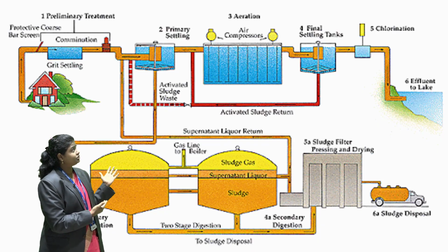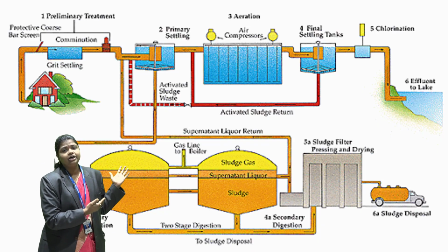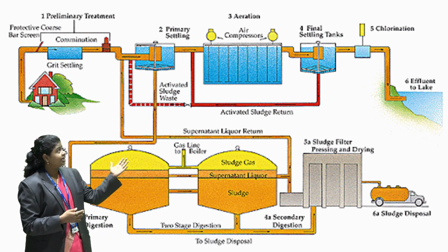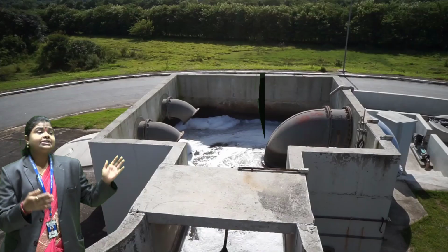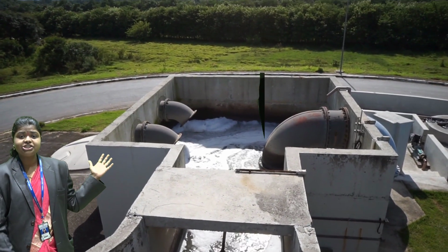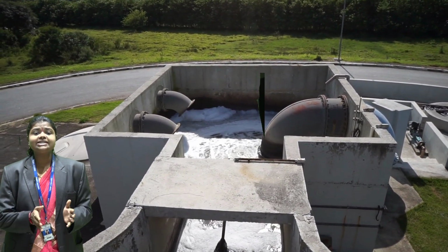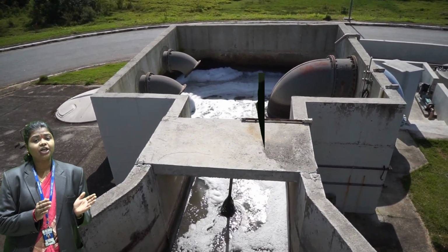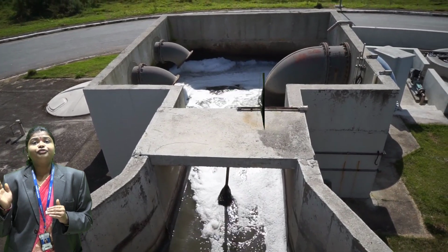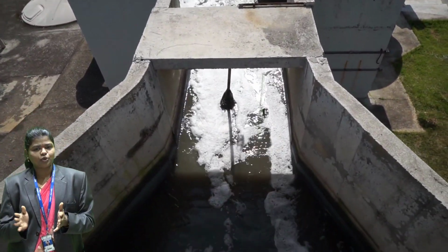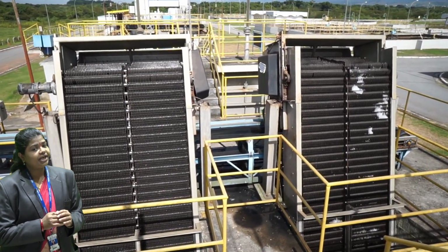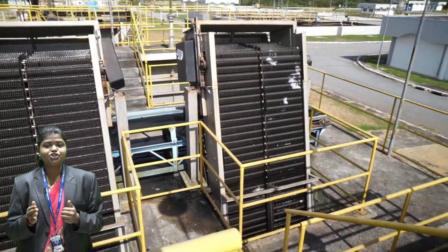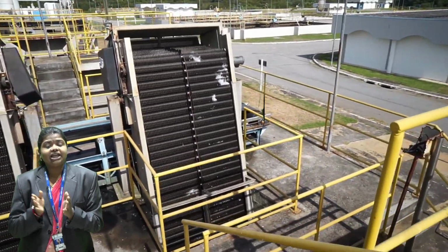This is a conventional wastewater treatment plant flow sheet in which we can see various preliminary treatments, primary treatments, secondary treatments and tertiary treatments. This is a diagram of a screen chamber, in which we can see a unit operation that separates large floating material in or on water from entering water treatment and wastewater treatment. Screens are provided to protect pumps, valves, pipelines and other apparatus from damage or clogging by rags and other large objects.